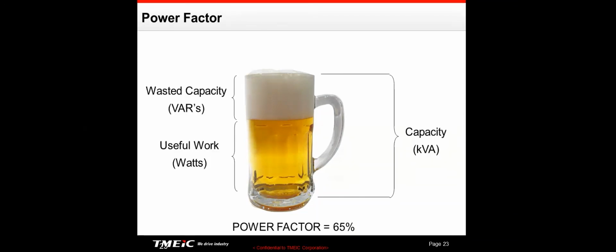Displacement power factor, and really all power factors are similar to this, in that the useful work we get out of current is what we call watts, and the wasted capacity, that would be the foam, would be VARs, and then those two together are the kVA. So if we look at it in terms of amps rather than volt amps, if you have 100 amps, you might find that only 65 of those amps are actually doing real work, and the rest of them are just being used for magnetization and harmonics and things of that sort.